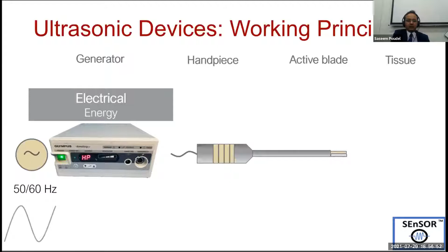These high frequency waves travel to the handpiece, and in the handpiece there is a piezoelectric disc that converts the electrical energy to mechanical energy of the same frequency, 23,000 to 55,000 depending on the machine you are using. This is then transferred to the shaft, where it is amplified and then transferred to the active blade, which causes the vibration.